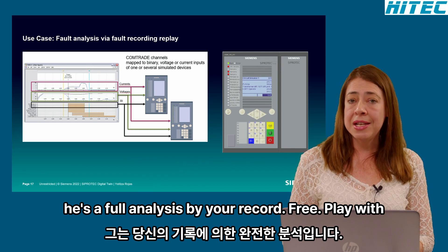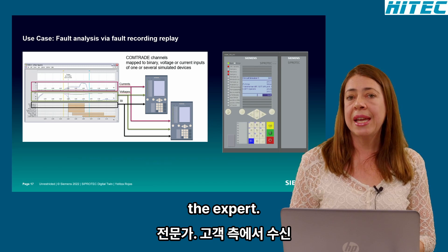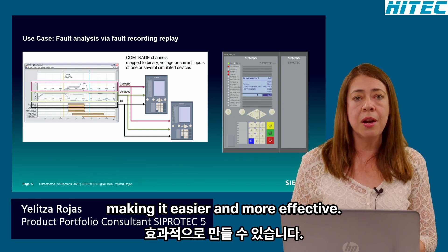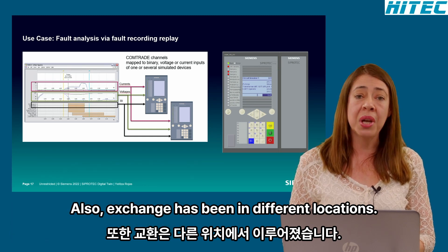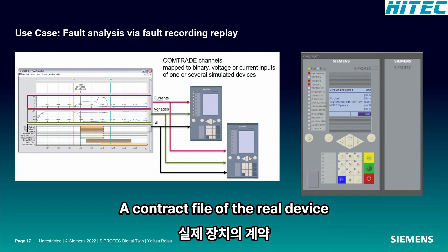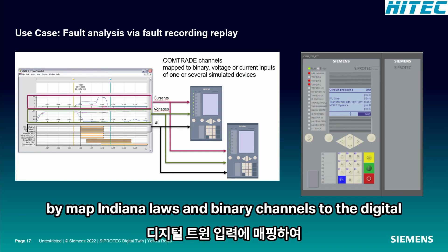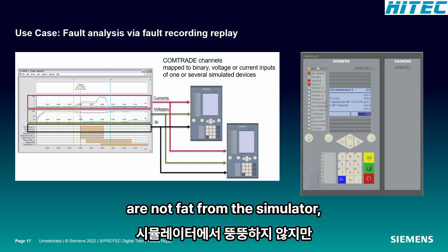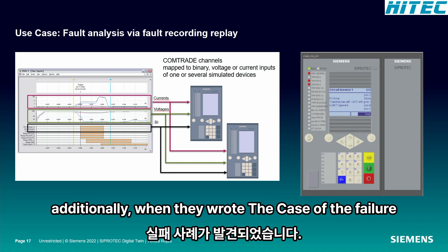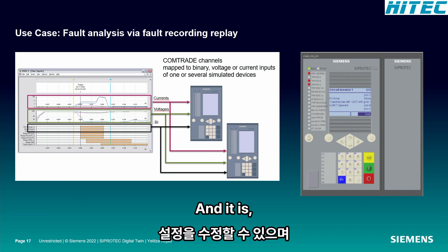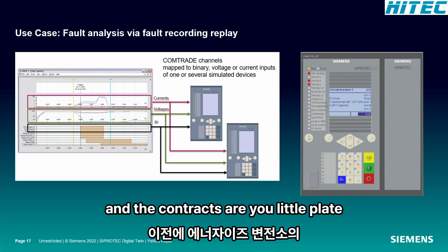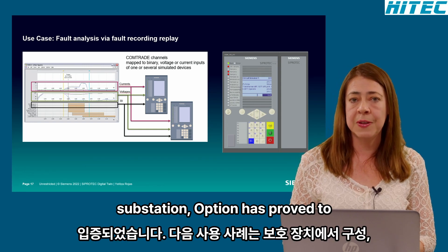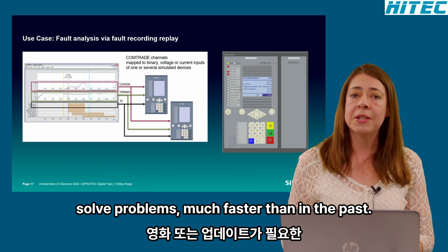The next case is fault analysis via record replay. With this option, the expert — either from customer or Siemens side — is able to see the response of the device, making the analysis easier and more effective. Two parties can also exchange findings in different locations far away from the installation. The Comtrade file of the real device is retrieved and replayed virtually by mapping the analog and binary channels to the digital twin inputs — the inputs are fed from the Comtrade, not from the simulator. Additionally, when the root cause of the failure is found and it is, for example, a wrong setting, this setting can be modified and the Comtrade can be replayed to verify the changes are satisfactory before updating the parameters in the energized substation.